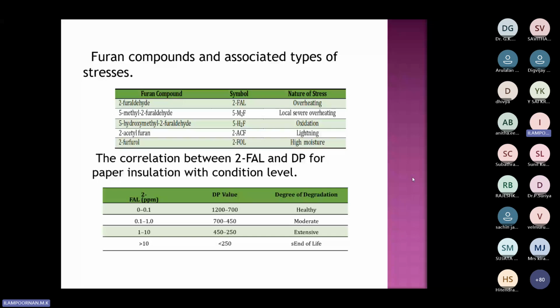Can you relate it? I'm not directly touching the paper - I'm only taking the oil, and testing the ppm level of 2-furaldehyde in it. If the 2-furaldehyde is in the range of 0 to 0.1, the DP value is good and healthy, above 700. If it rises to 1 ppm, the DP value falls. It's an indirect correlation - when FAL rises, the DP value decreases, meaning more compound is getting depolymerized.